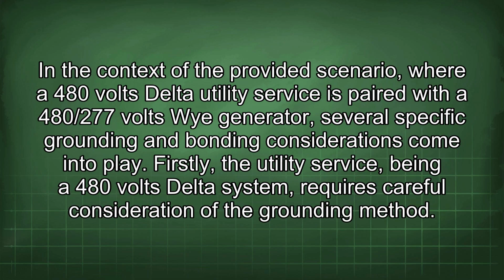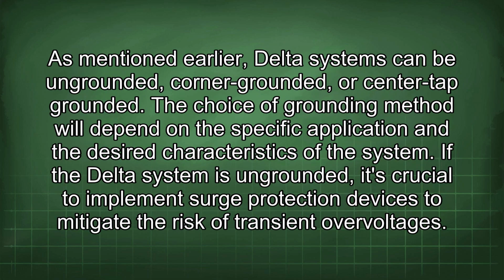In the context of the provided scenario, where a 480 volts delta utility service is paired with a 480/277 volts Y generator, several specific grounding and bonding considerations come into play. Firstly, the utility service, being a 480 volts delta system, requires careful consideration of the grounding method. As mentioned earlier, delta systems can be ungrounded, corner grounded, or center tap grounded. The choice of grounding method will depend on the specific application and the desired characteristics of the system.